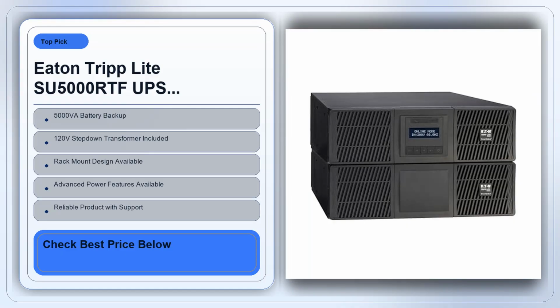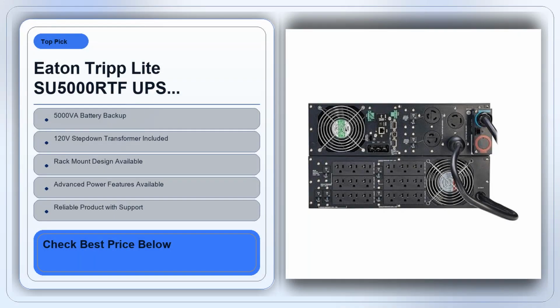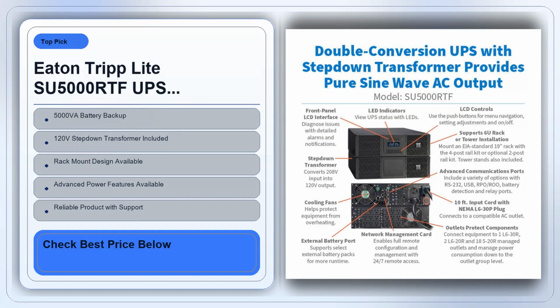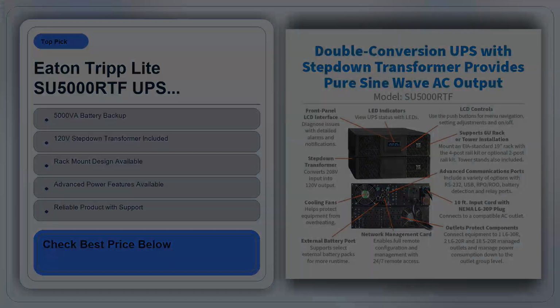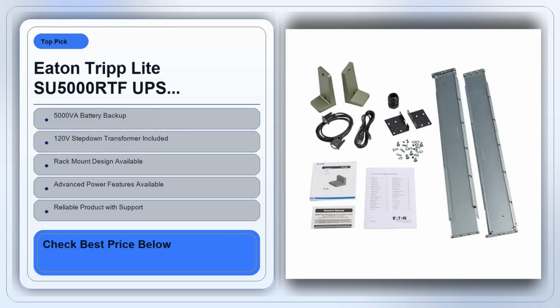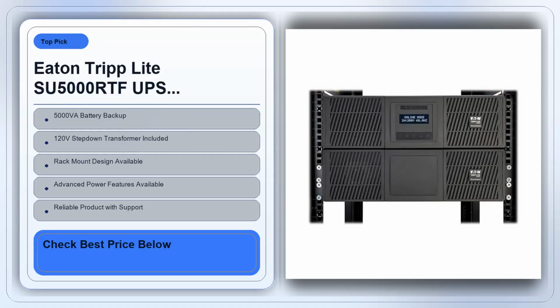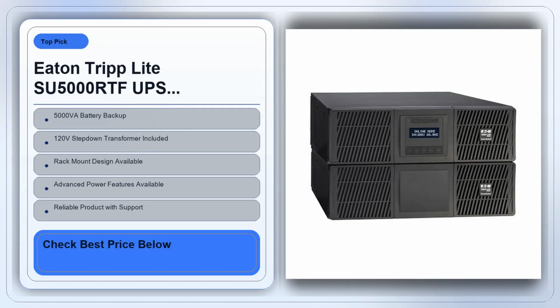Who should skip it? If you're only looking to protect a single desktop or a modest home entertainment system, you're overpaying. A smaller line interactive unit would handle a single PC and a TV just fine and would be far lighter. Likewise, if you run a large data center with multiple megawatts of load, you'll need a higher capacity, modular UPS that can scale beyond 5 kVA, and you'll probably be looking at a solution with hot swap batteries built into the rack. In terms of weaknesses, the biggest complaint I've...